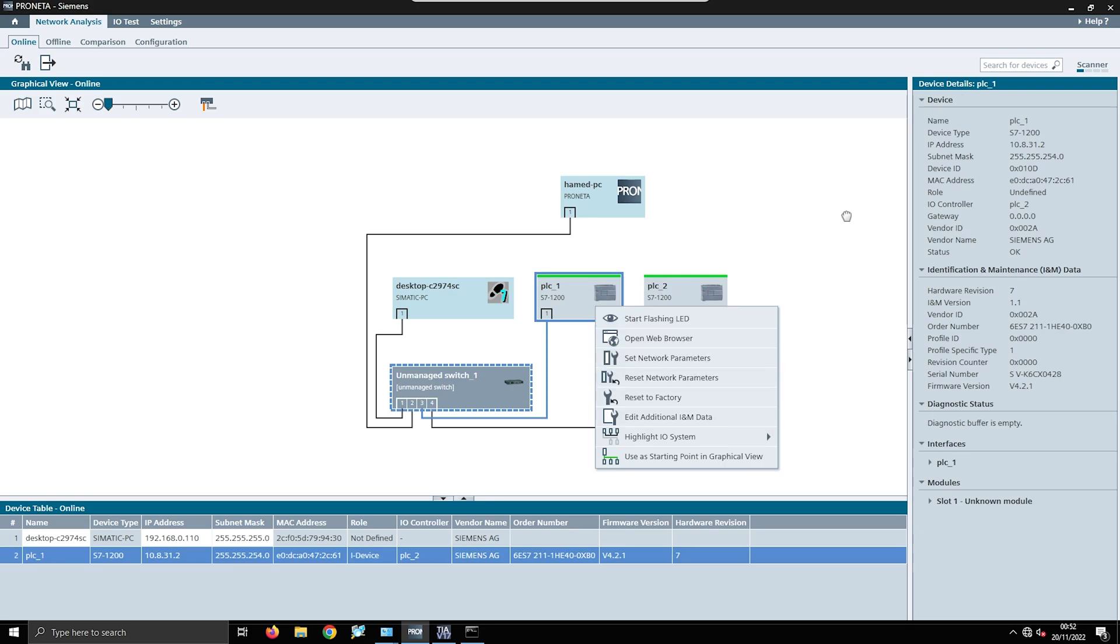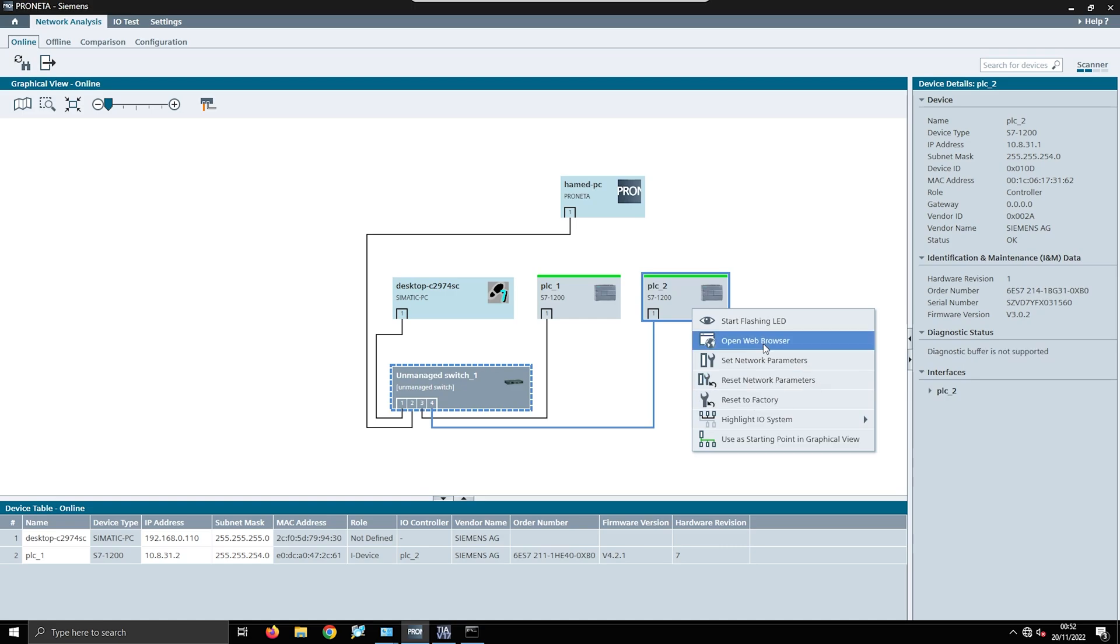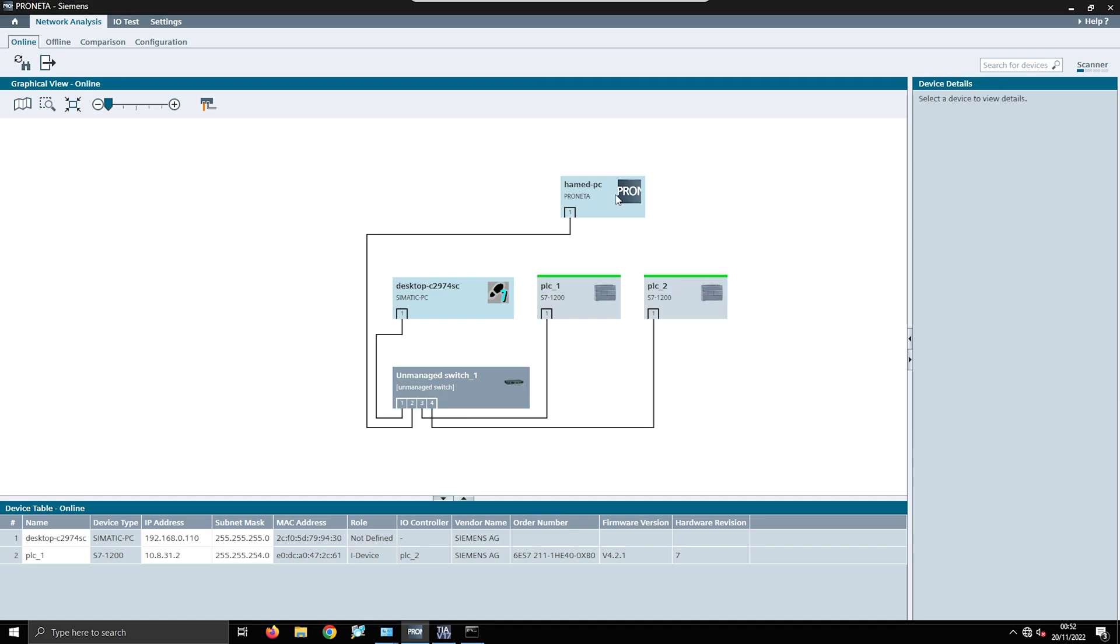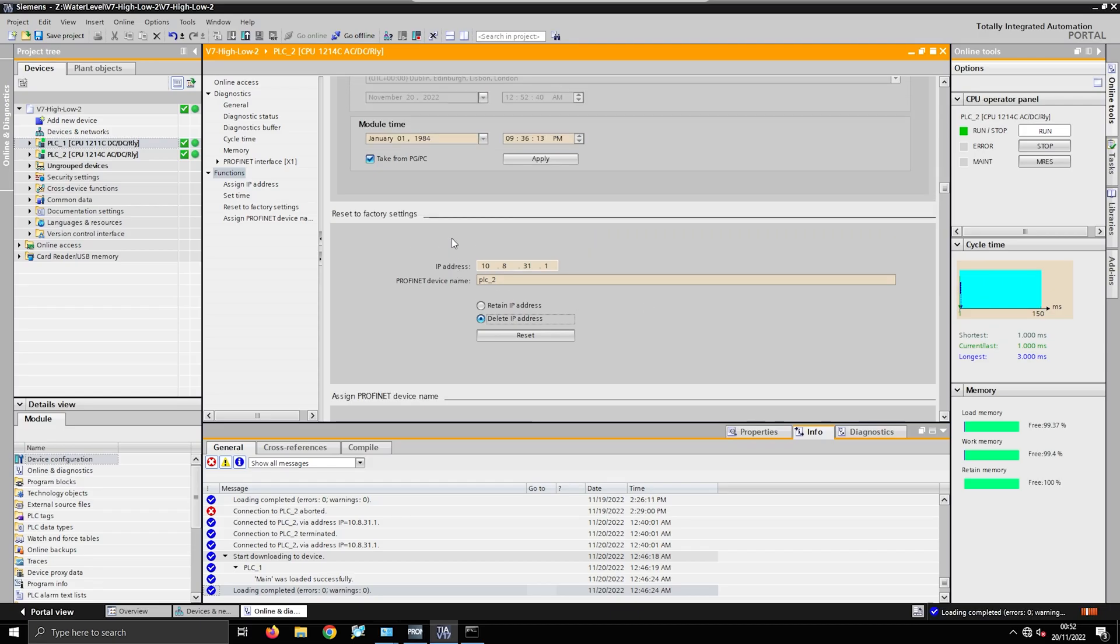Then you're able to go into Proneta, which is a good Siemens software to use, and then you can actually just right-click and set your network parameters. You can do a bunch of different things - reset to factory again, open web browser, start flashing LEDs, a bunch of different stuff. As you can see here I've got my PC and it's going to an unmanaged switch, and then I've got my two PLCs there. That's how I solved my duplicate IP issue.